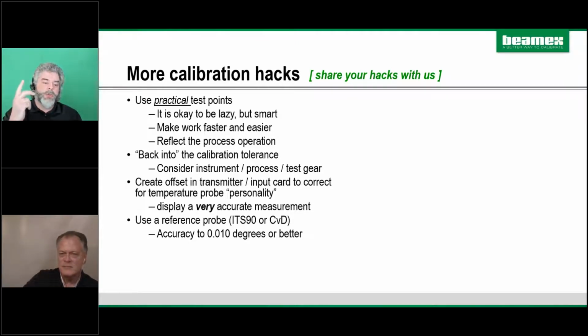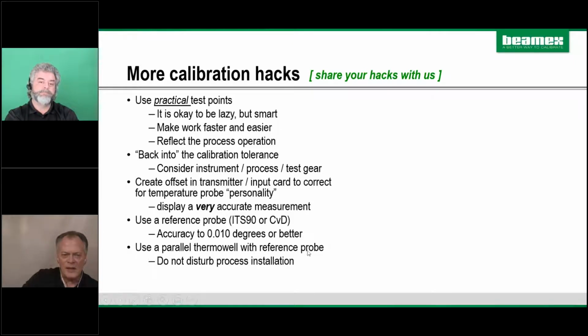Yeah. So, all right, I lost my train of thought. What I was going to say was, every dry block is accurate to a certain value, and you can usually increase that accuracy by using a higher performance or more accurate temperature probe as your standard in that dry block or bath. And that's Ned's whole point here with using a reference probe. You can upgrade the accuracy of your temperature measurement by using a high accuracy probe. Very good. Okay, we're getting to the end here.